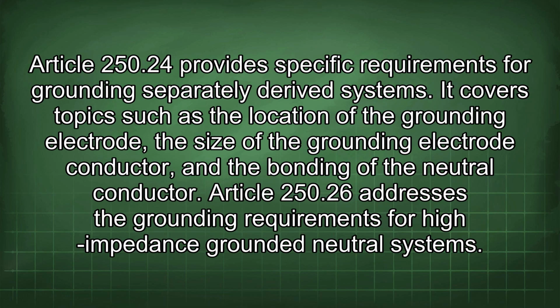Article 250.24 provides specific requirements for grounding separately derived systems. It covers topics such as the location of the grounding electrode, the size of the grounding electrode conductor, and the bonding of the neutral conductor.